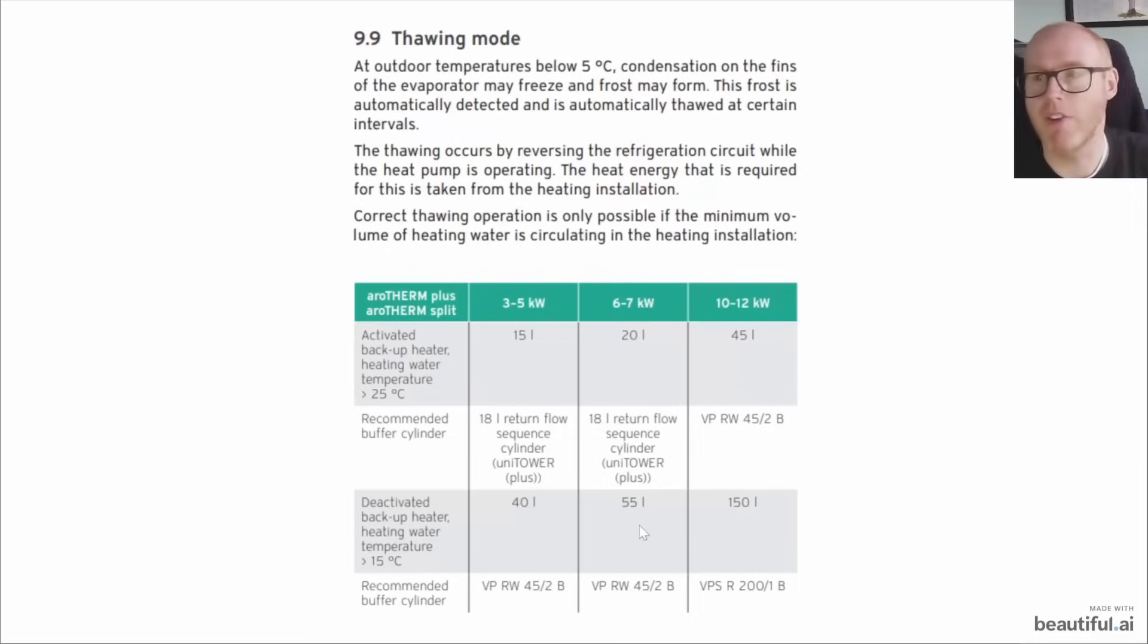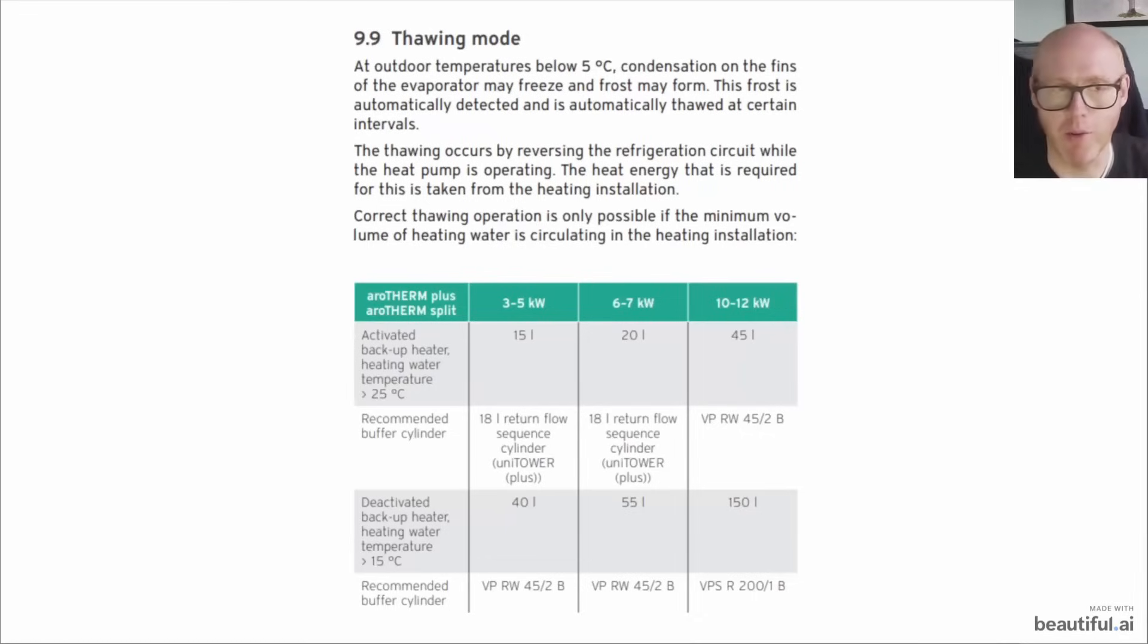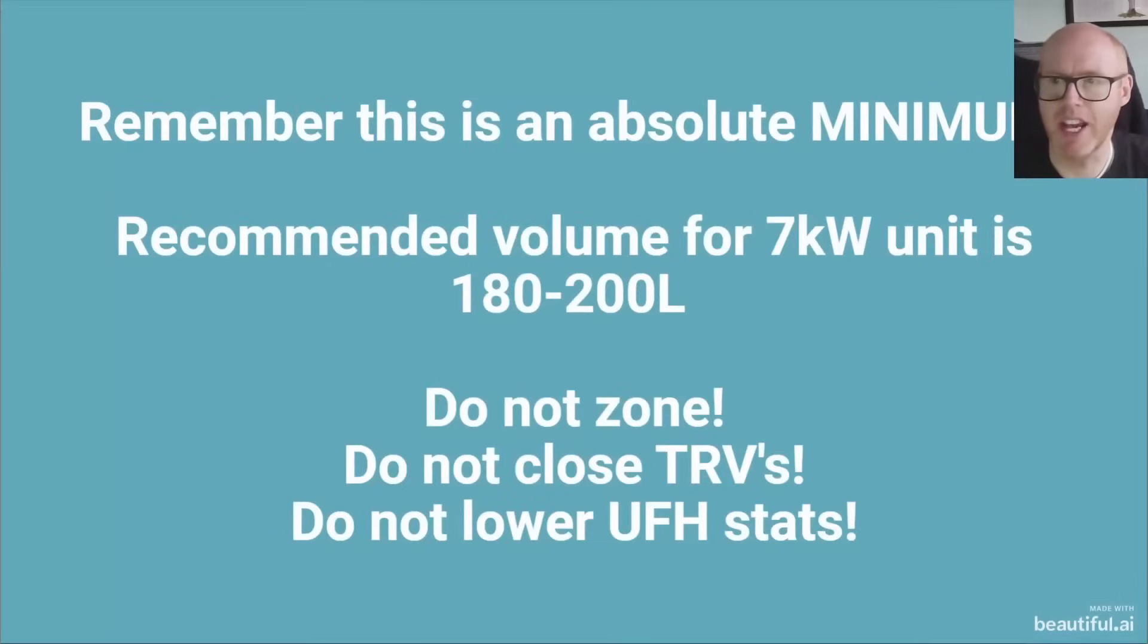There's many variables, but that gives us a little ballpark. A lot of people look at the manual and they go, oh 55 litres, that's all I need for a 7 kilowatt Arotherm Plus, but they can quickly run into problems if they are at that sort of level. We have heard of this death spiral and end of the world scenarios, but remember that this is an absolute minimum of 55 litres.